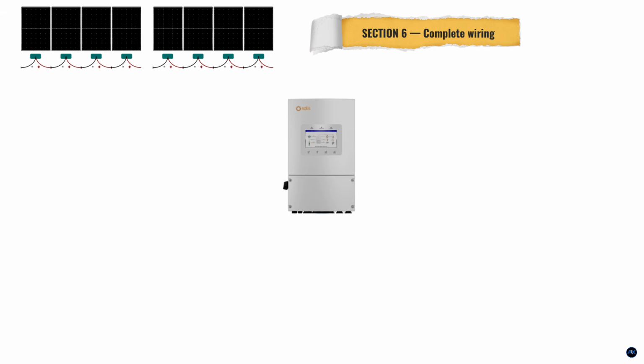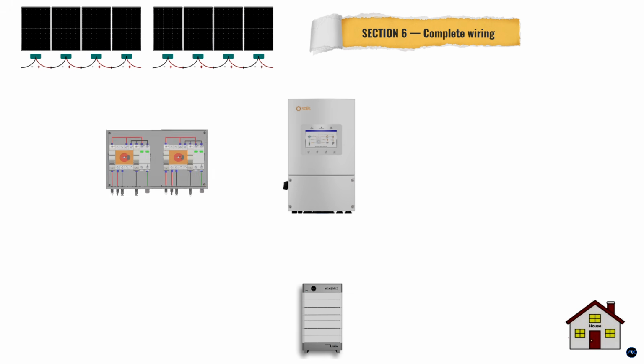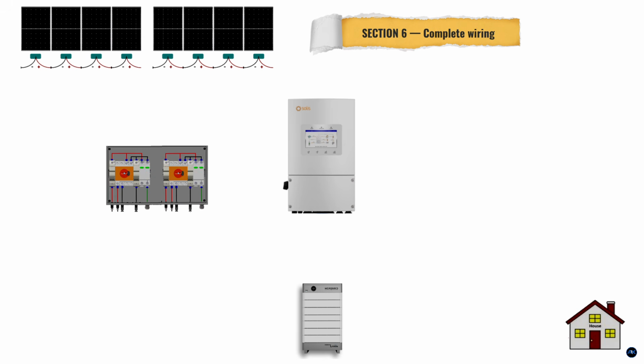8 580-watt solar panels, a Solis 6 kilowatt hybrid inverter, 7 lithium iron phosphate batteries, 33 kilowatt hours of storage, 1 fully protected home. Let's wire it. Step 1. DC solar and combiner box. Your 8 panels form 2 strings, 4 panels in series, 2 strings in parallel.